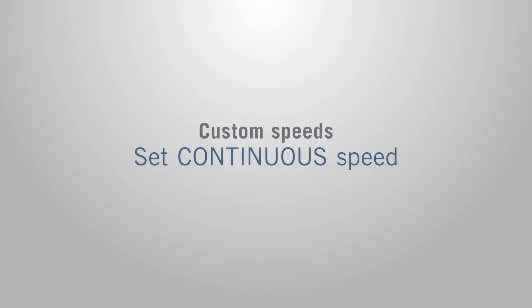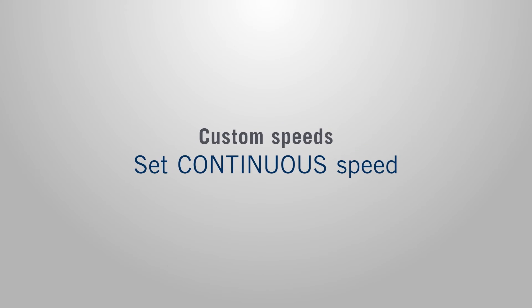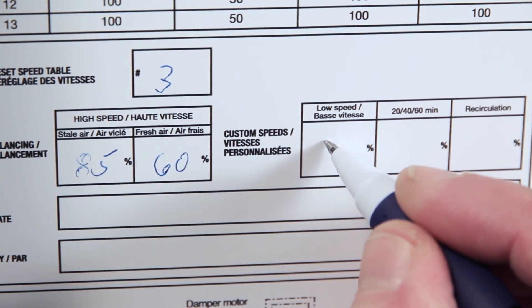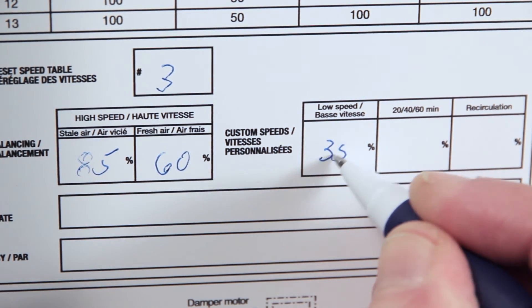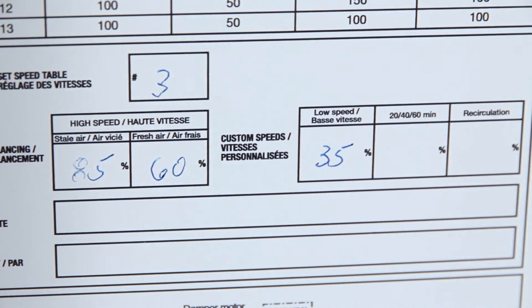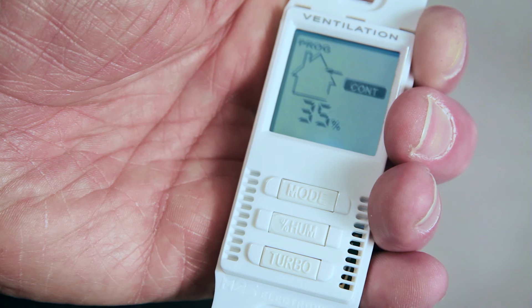If you have chosen custom speed, adjust the airflow to the desired CFM value. Press the upper button to raise the value. Take note of the setting value at this step, as it will disappear by pressing the accept button. Press the middle button to accept the chosen percentage.